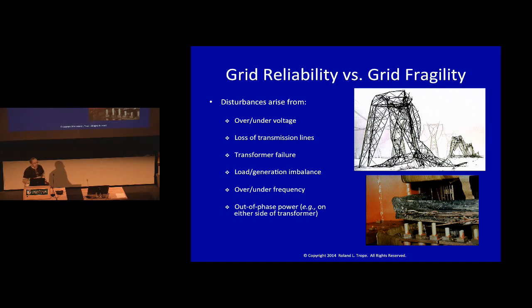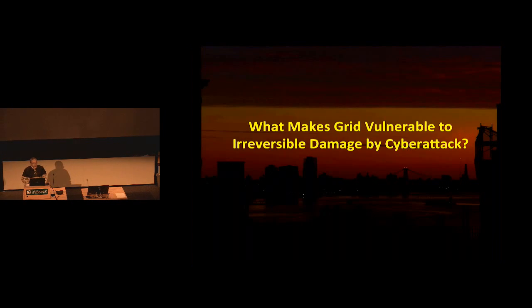If there's that load generation imbalance I've been discussing, or if there's under or over frequency, or out of phase power - which is, for cyber purposes, one of the most important - because if you can get power to be out of phase on either side of the transformer just near a generation plant, you can perhaps damage the transformer and perhaps destroy the generation plant, losing a big generation plant in a part of the grid, and it will be very hard for them to react in time to prevent cascading outages.